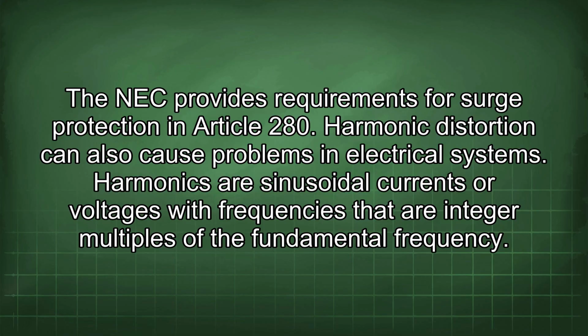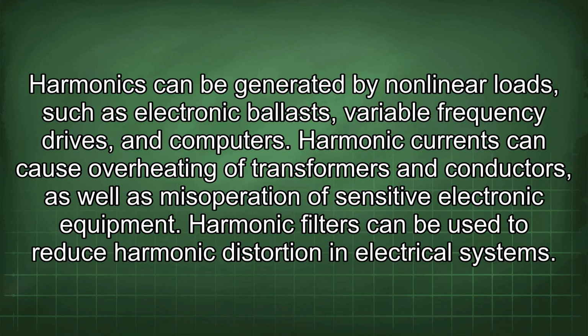Harmonic distortion can also cause problems in electrical systems. Harmonics are sinusoidal currents or voltages with frequencies that are integer multiples of the fundamental frequency. Harmonics can be generated by nonlinear loads such as electronic ballasts, variable frequency drives, and computers. Harmonic currents can cause overheating of transformers and conductors, as well as misoperation of sensitive electronic equipment. Harmonic filters can be used to reduce harmonic distortion in electrical systems.